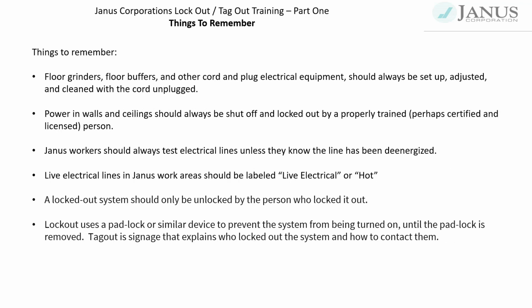Things to remember about lockout tagout. Floor grinders, floor buffers, and other cord and plug electrical equipment should always be set up, adjusted, and cleaned with the cord unplugged. Power in walls and ceilings should always be shut off and locked out by a properly trained, perhaps certified or licensed person. Janus workers should always test electrical lines unless they know the line has been de-energized. Live electrical lines in Janus work area should be labeled live electrical or hot.